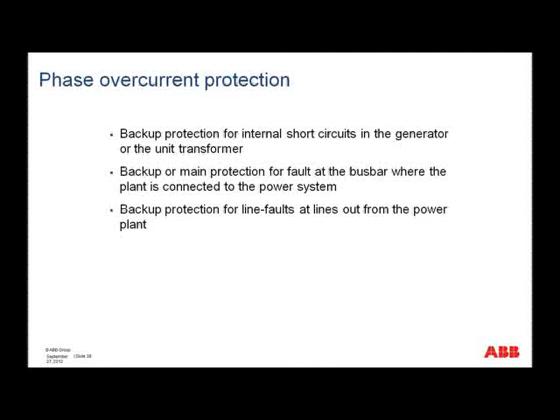Turning now to the phase overcurrent protection, if you look at the bullet points here, you'll see they are very similar to what was said for the under-impedance. So we're talking about backup protection for internal short circuits in the generator or unit transformer, primarily though for current fed from the network side. Backup or main protection for fault at the bus bar where the plant is connected to the power system, and also backup protection for line faults at lines out from the power plant.